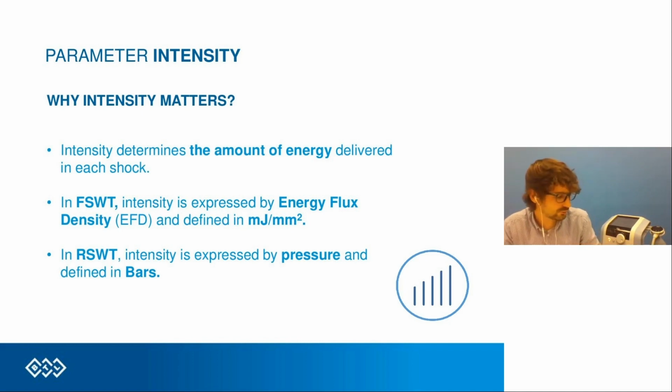And just for this basic seminar, it's important just to know that there are differences between the two technologies. For example, it is not possible to compare bars to EFD, to this millijoules per millimeter square, because as I mentioned, the bars are inside of the radial shockwave device, whereas the EFD is outside with the focused shockwave device.